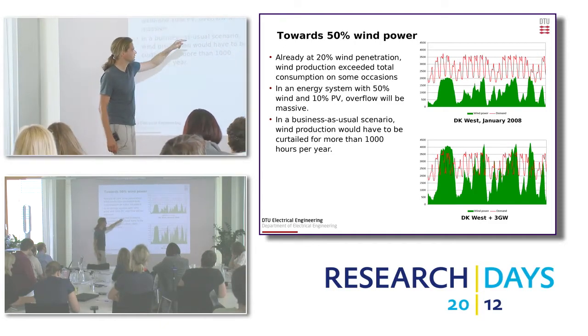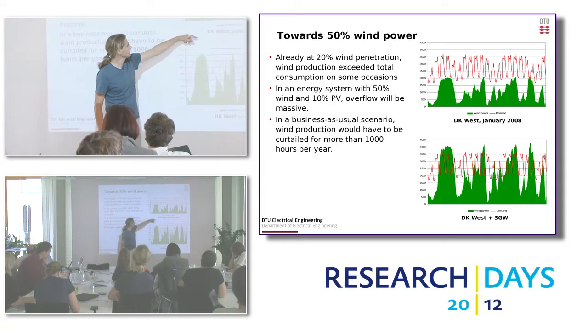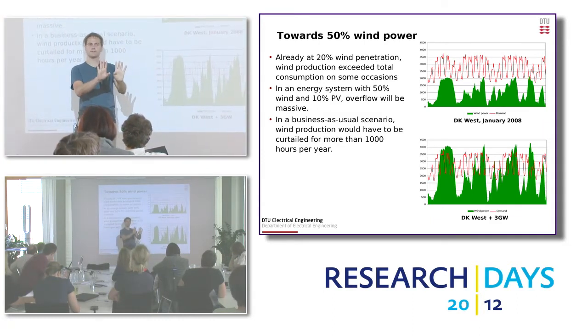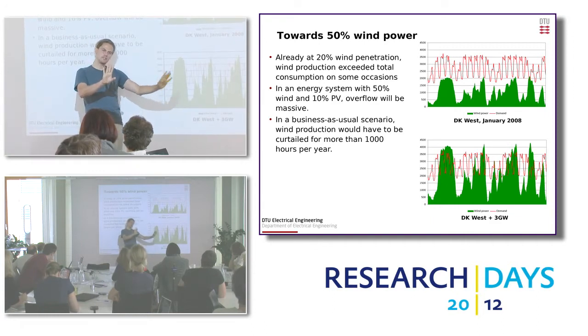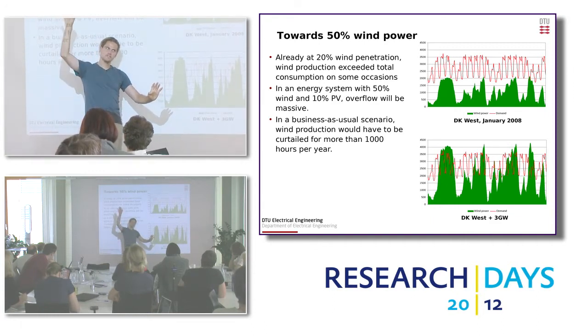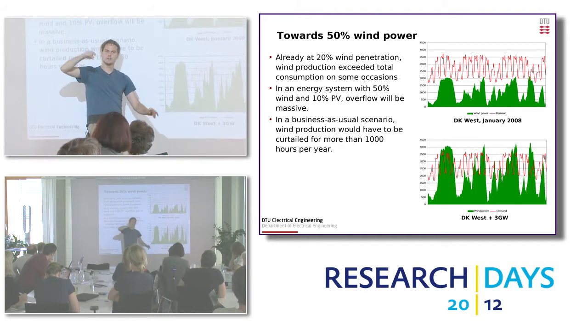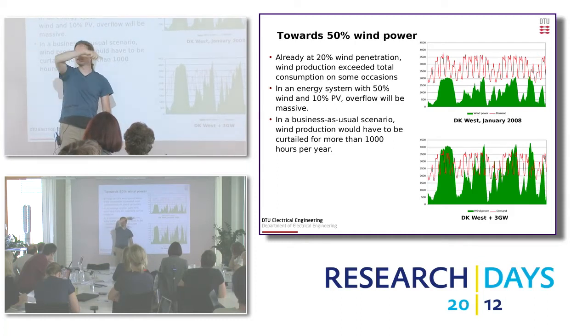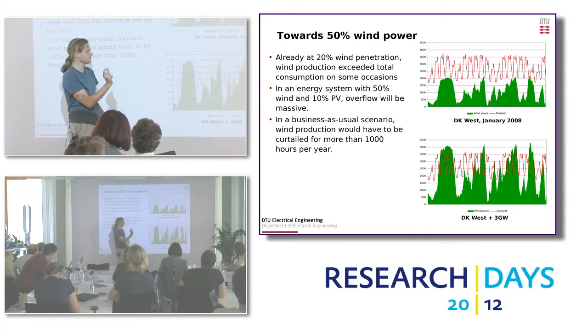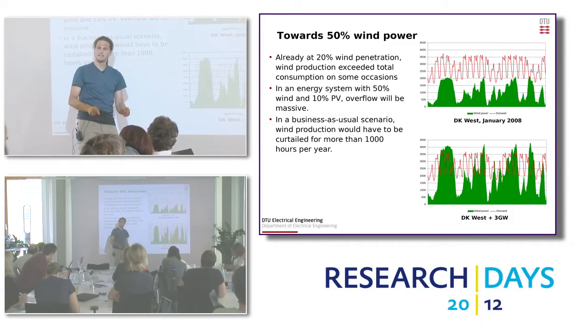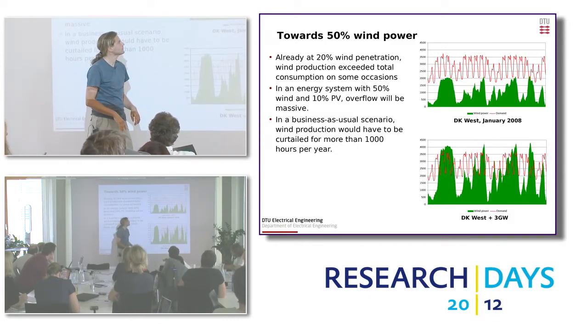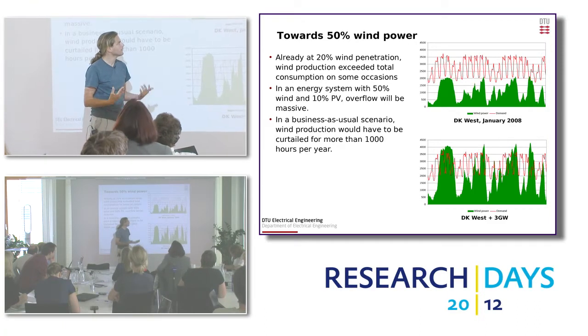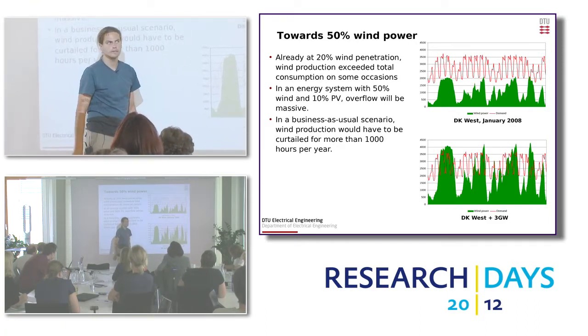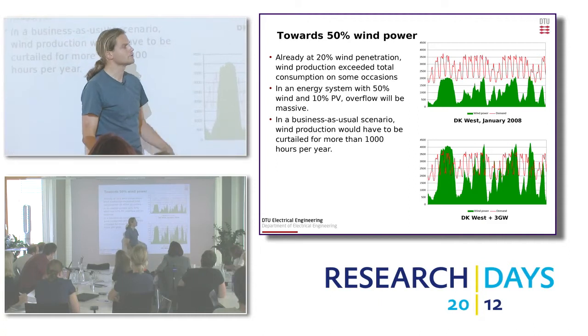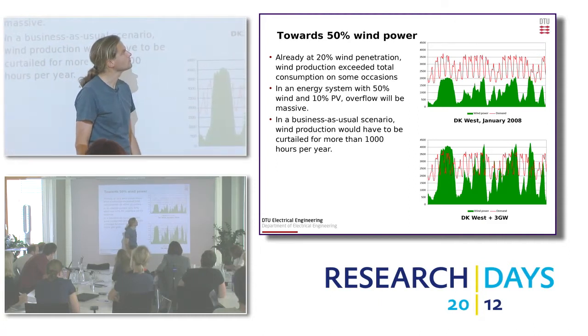If we assume we add more, this is the western part of Denmark - I should say we have 2 power systems. One is connected to the continent and one to the Nordic system. Until last year they weren't electrically connected, so they could only indirectly exchange energy through Sweden or Norway. Now the Great Belt DC cable has been provided between these 2 systems, but since they don't share the same frequency, they are kind of independent control areas. This is for the western part of Denmark, where the majority of wind power is installed.